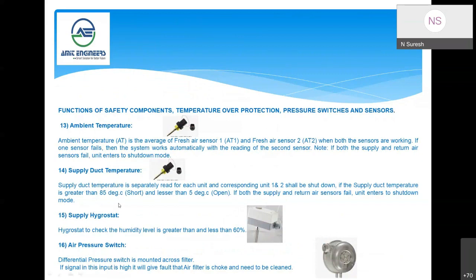Whereas in LHB coaches there was only one hygrostat, in this unit each unit has an independent hygrostat, that is the humidity sensor. The RH percentage will be continuously monitored, and a signal provided to the system controller. Accordingly, the compressor will be working. Compressor and heaters will be working.